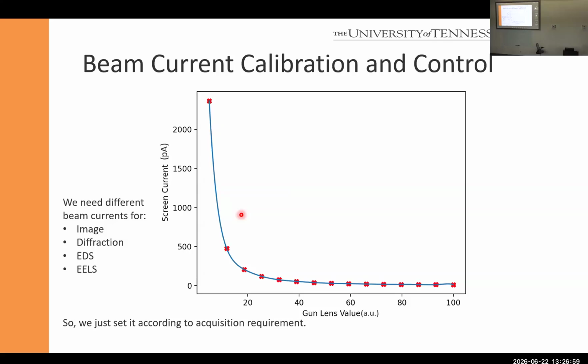For EELS, it depends on your sample, and you want to change that very quickly. If you watch me changing that, I put the screen in. I have to change the button to the gun lens, right? And then I focus till I am there. That takes a while. By that time, I have possibly destroyed the sample or something else moved away. Who knows, right? Things can happen. It certainly is slow. And if I go between diffraction pattern and EDS spectrum backwards and forwards, we can talk about a minute. So it's not going to happen very often just because I don't want to do it.